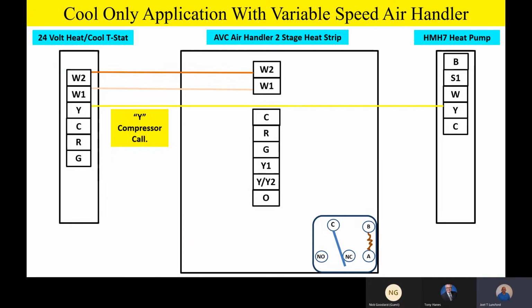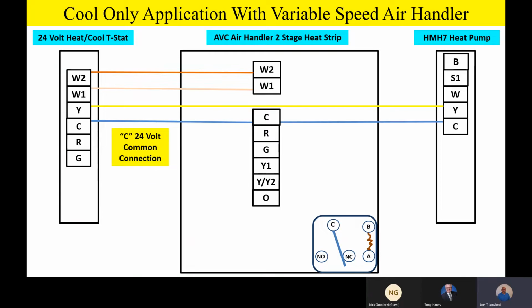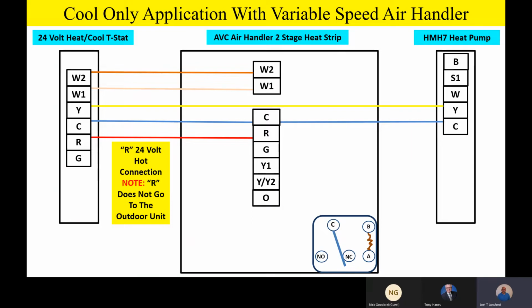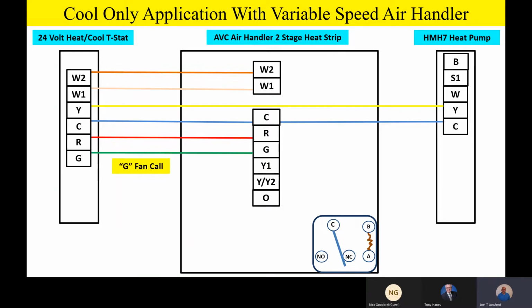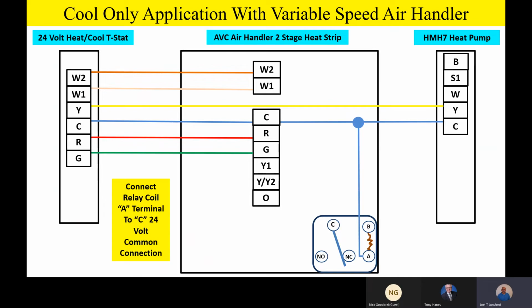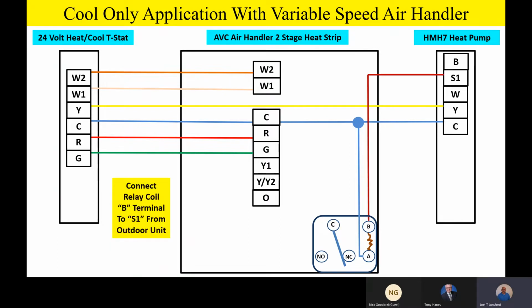Y terminal is going to go straight outside, just like we had before. C terminal is going to go all the way through, 24 volt common. That 24 volt hot, that R terminal, is going to go just to the air handler, and G will be our fan call, just like we had before. Now, this is going to give you airflow reduction on this variable speed air handler by taking the coil of that single pole double throw relay. One side of the coil goes to common, the other side goes up to S1.